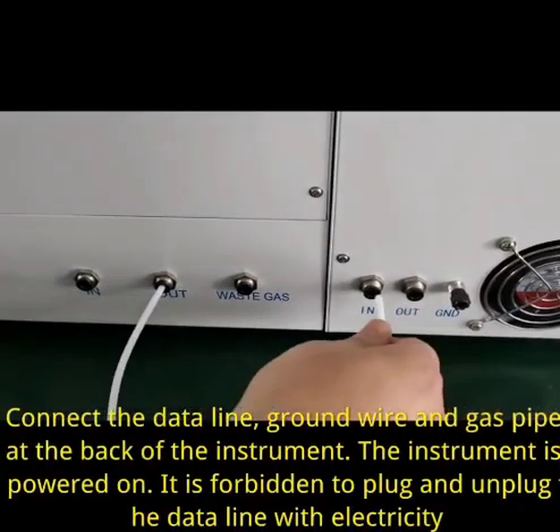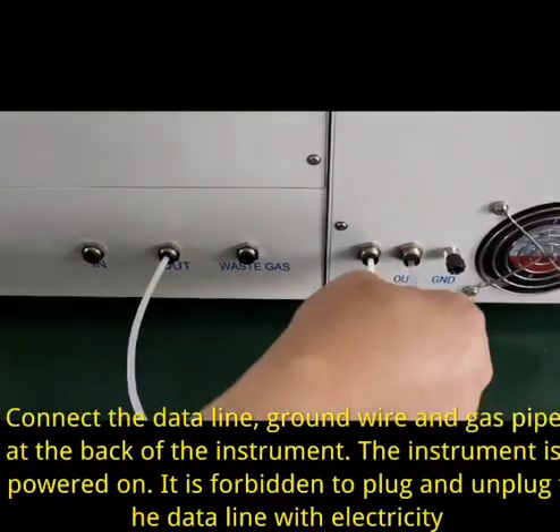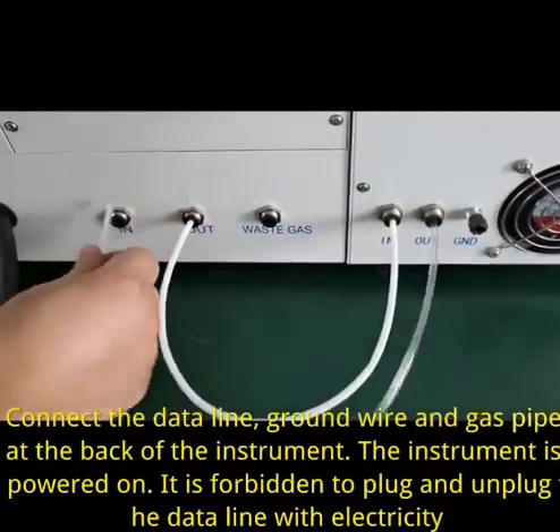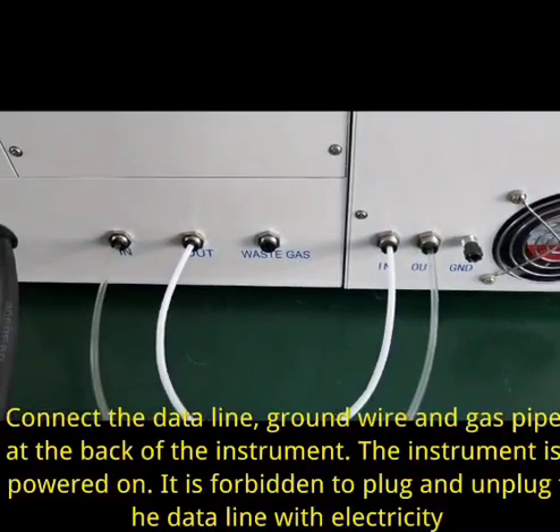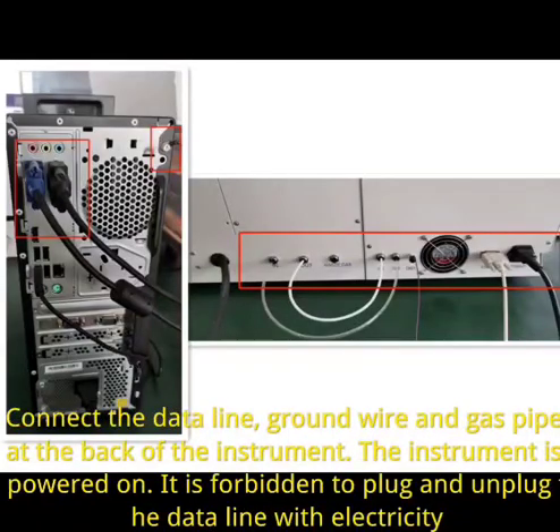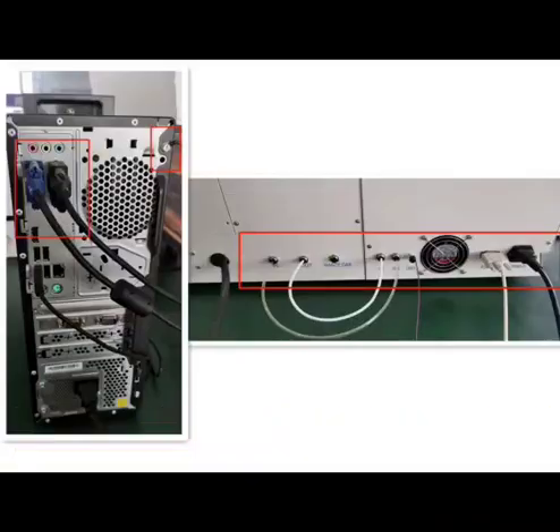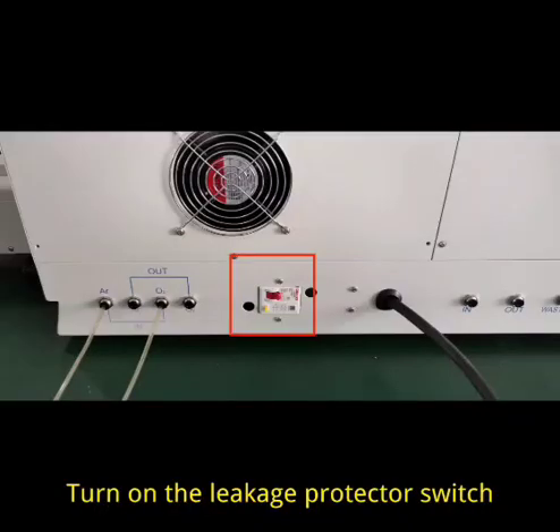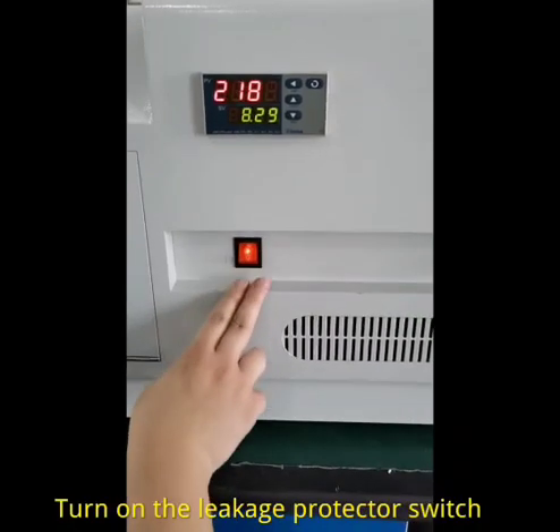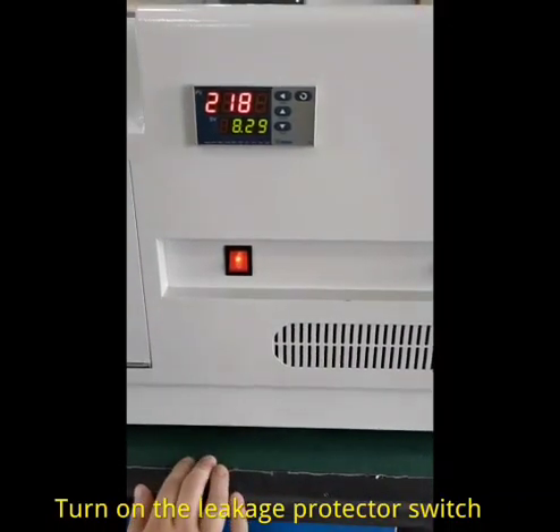High temperature furnace temperature commissioning. Connect the data line, ground wire and gas pipe at the back of the instrument. The instrument is powered on. It is forbidden to plug and unplug the data line with electricity. Turn on the leakage protector switch.